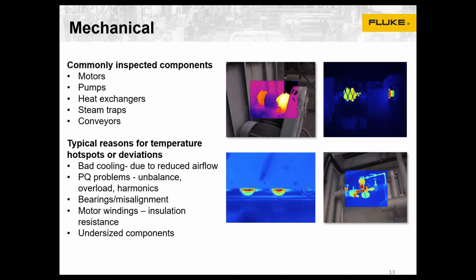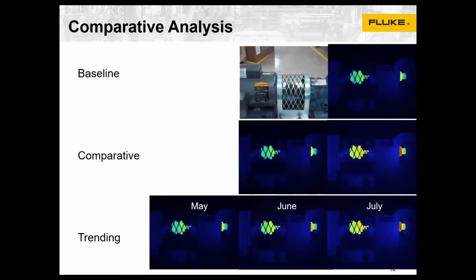But thermal imaging is fast, non-contact, and works very quickly. It makes a great screening tool in a lot of situations. Here are three different approaches that you could use on site. One is certainly if a piece of equipment is brand new, you can baseline it or capture images that you can use for trending purposes down the line. Even if your equipment's not new, you have to start somewhere. You can take an image and see what it looks like today.